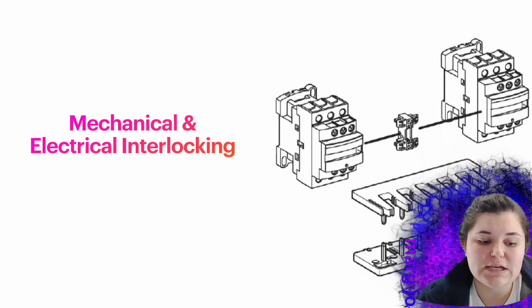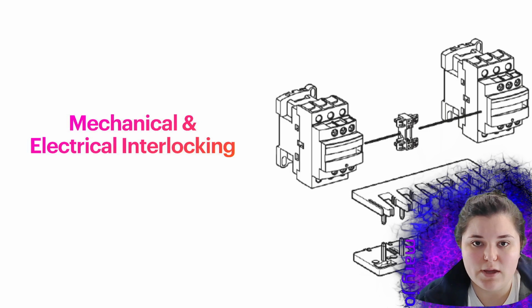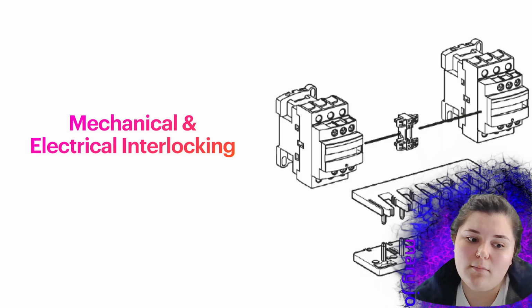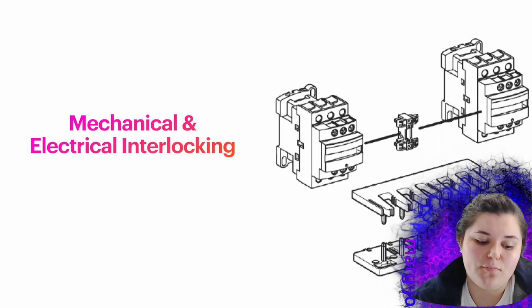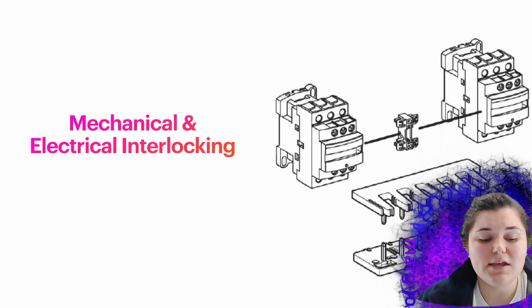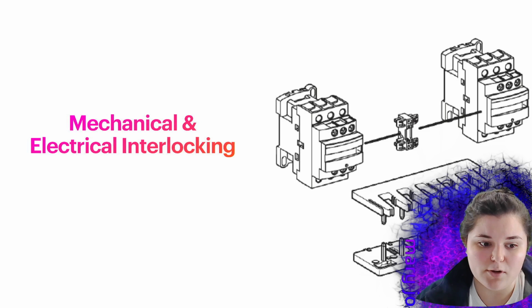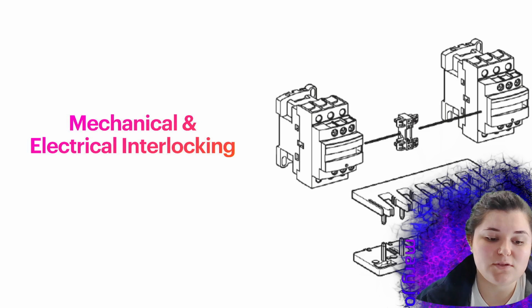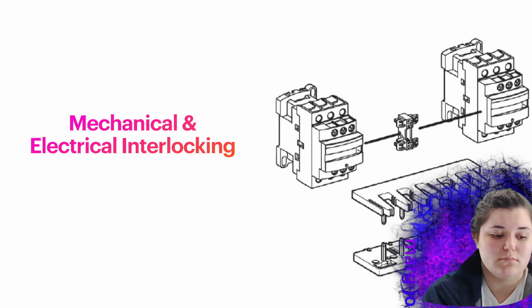So whenever that's energized, it should create an electrical interlock, depending on how you wire it up. And that's going to prevent you from pushing both buttons at the same time. That means you cannot run that motor in forward or reverse at the same time, because that's going to burn up the motor if you try to do that. So this is wired up in a way that the electrical interlock should prevent you from doing that. But if it ever did fail, then that mechanical interlock is going to prevent it, and it's going to make an awful noise, and you're going to know that something is wrong with that mechanical and electrical interlock.